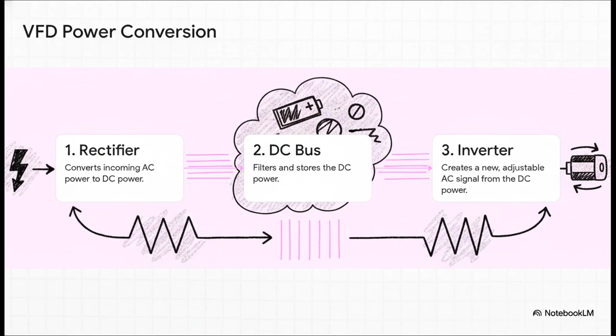A soft starter controls only the voltage, and only during startup. After that, your motor is stuck at one fixed speed. A VFD, on the other hand, controls both voltage and frequency, continuously. That means your motor can run at pretty much any speed you tell it to, at any time.